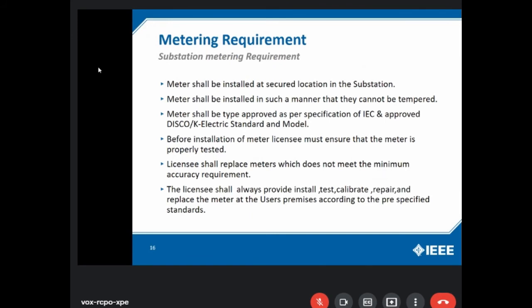Substation metering requirement. A meter shall be installed at a secured location in the substation. The discos demand a separate metering room for this purpose, having exclusive right of entry into the substation. Metering shall be installed in such a manner that it cannot be tampered with. It should be properly sealed, signed by both the distribution company and the consumer representative as well. This is what we have discussed in the last slides.